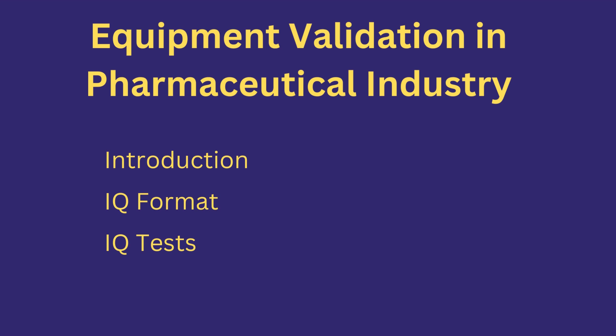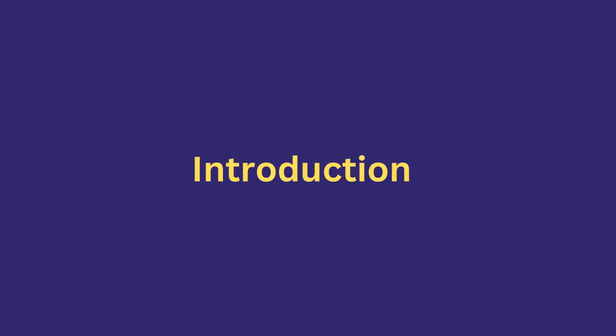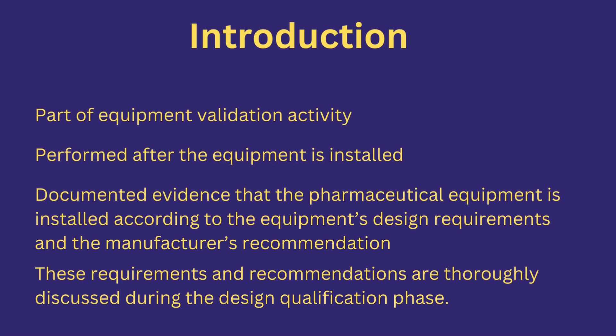IQ checklists are included in a typical installation qualification. Note that every pharmaceutical equipment has its own dedicated IQ test that cannot be replicated for others. The tests we will discuss are common to every equipment or machine in the pharma industry. Installation qualification is a part of validation — it is performed after equipment is installed but before production has started and before conducting operational qualification.